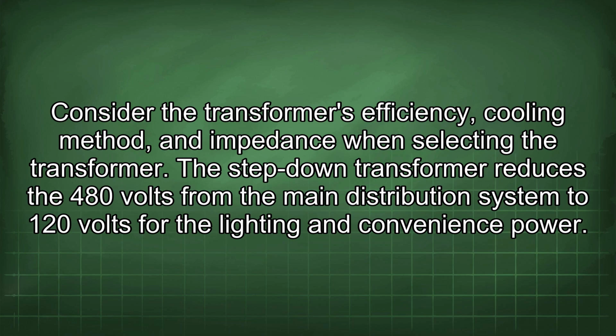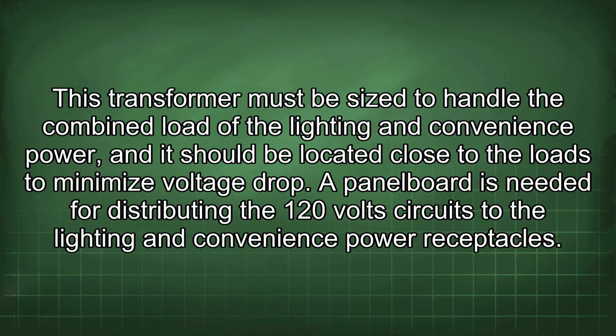The step-down transformer reduces the 480 volts from the main distribution system to 120 volts for the lighting and convenience power. This transformer must be sized to handle the combined load of the lighting and convenience power, and it should be located close to the loads to minimize voltage drop.